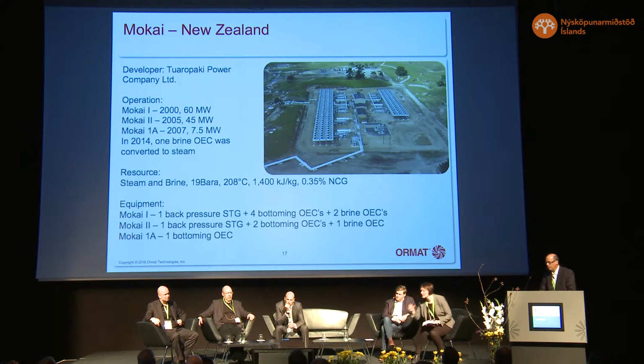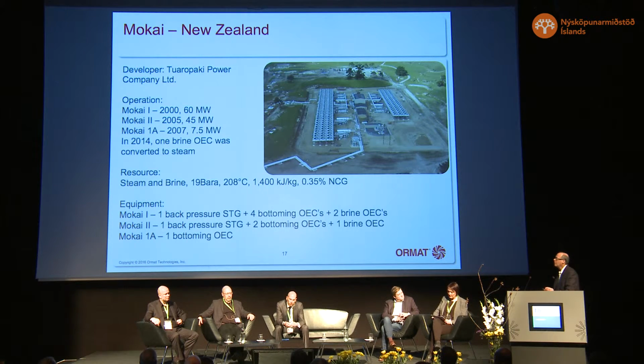And what we can see here, and this is one of the benefits, is that, first of all, throughout the years, due to the 100% reinjection, the power plant saw an increase in enthalpy. Seven years after the installation, they added another bottoming ORC, and seven years later, they changed one of the brine ORCs into a steam-fed ORC. And by that, of course, they increased the power output of the plant.